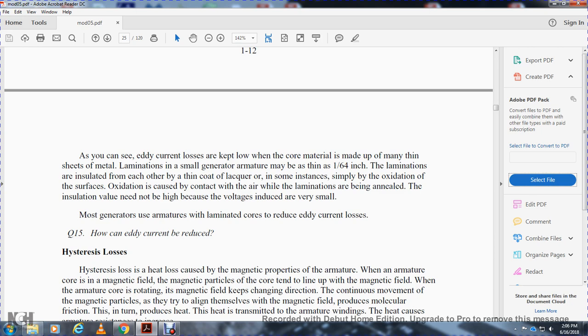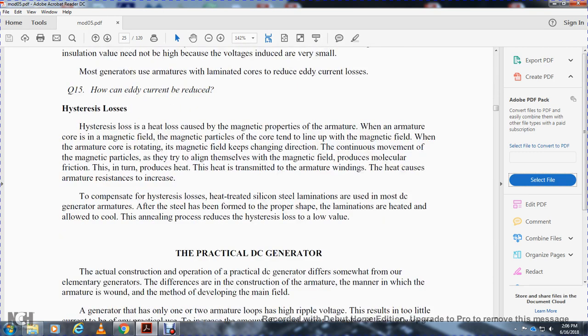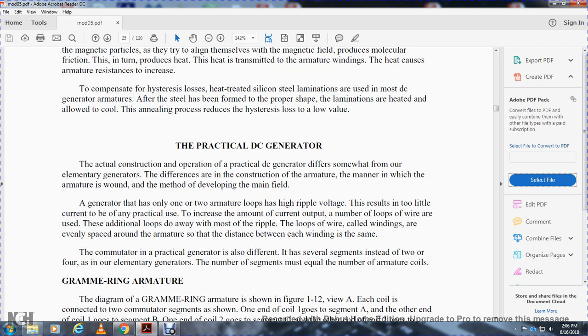The insulation value need not be high because the induced voltages are very small. Hysteresis loss: hysteresis loss is a heat loss caused by the magnetic properties of the armature core. The magnetic particles of the core tend to line up with the magnetic field as the armature rotates, producing molecular friction and heat. This heat is transmitted to the armature windings, and the heat increases armature resistance. Hysteresis loss is reduced by using heat-treated silicon steel laminations in almost all DC generator armatures. After the steel is formed to the proper shape, the laminations are heated and allowed to cool — an annealing process — to reduce the hysteresis loss.